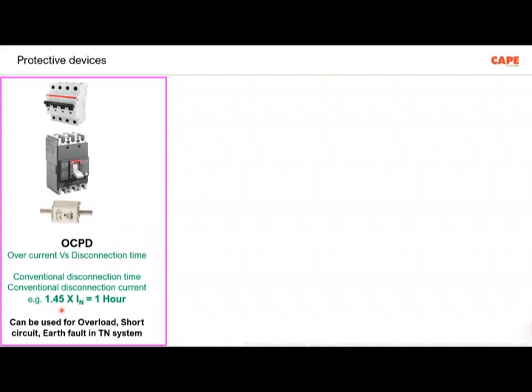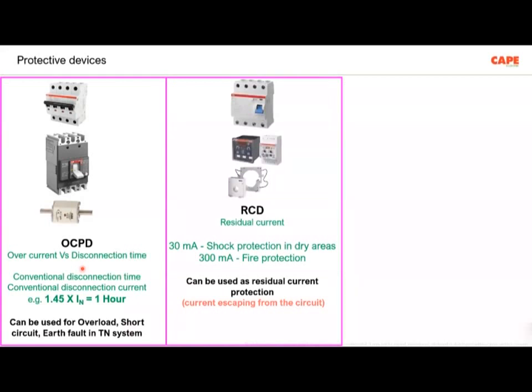What it means is you have a 10 amps MCB, your overcurrent is 14 amps. How much time will it take the MCB to trip? Up to 1 hour. So your electrical wiring must be able to withstand that much, the conventional time it is supposed to withstand. So in electrical design, we are supposed to take care of this particular subject. The overcurrent can be caused by overload, short circuit, or earth fault in a TN system. So OCPDs can be used against overload, short circuit, and earth fault in a TN system. Of course, overload and short circuit in all the systems and earth fault in TN system. Then the second protective device is called RCD, residual current device. We call it RCCB or CBCT plus the earth fault relay.